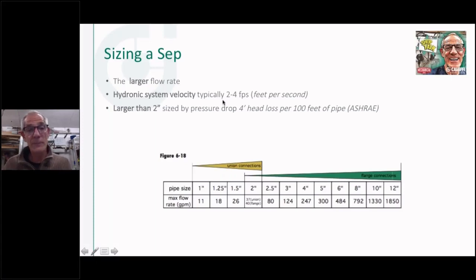And when we talked about the pipe sizing here on the last couple of webinars, we talked that typically in a hydronic system, we're going to run between 2 and 4 feet per second flow velocity. That does change a little bit when you get into larger pipe size. In fact, the ASHRAE standard shows that when you size larger pipe, you go by the head loss per 100 feet of pipe.